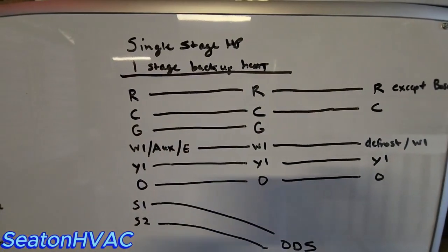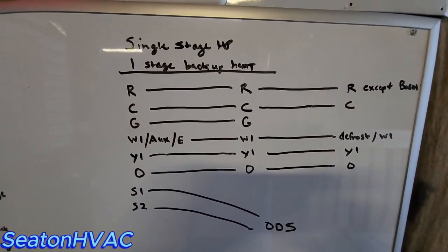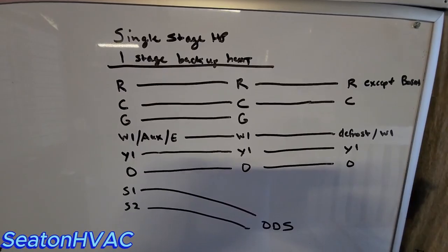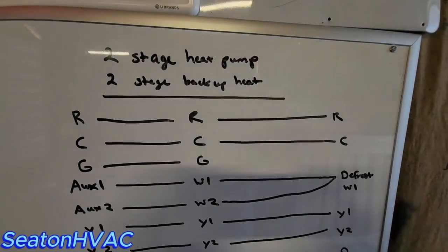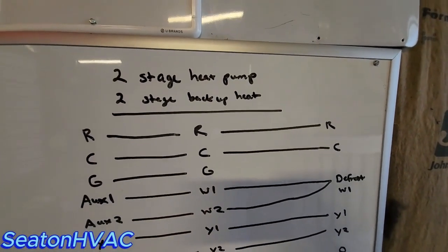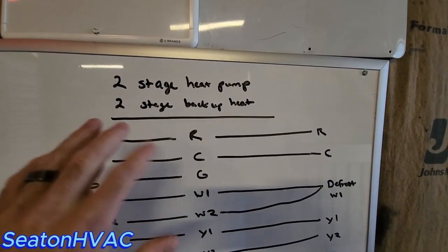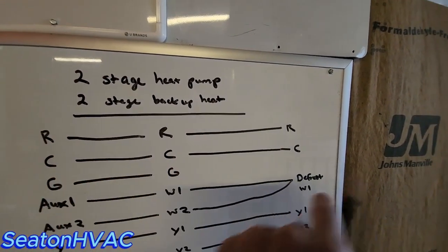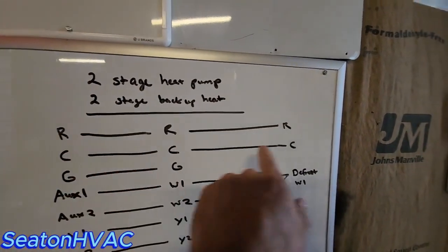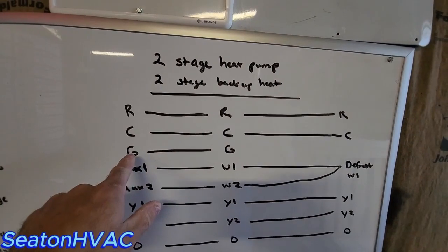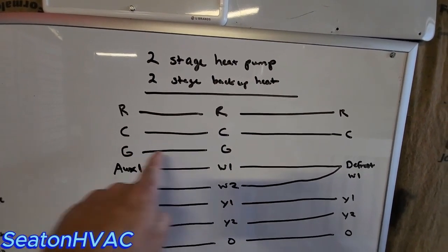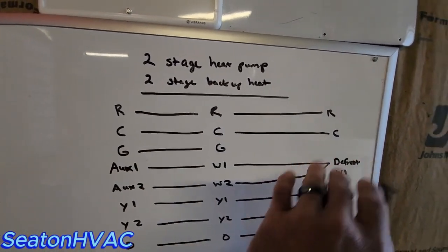Let's do a 4 heat, 2 cool scenario on this, so I can show you the most crazy setups that you'll see. Okay, guys, 2-stage heat pump with 2 stages of backup heat. So I'm not going to go over all this, and it's all the same. R all the way outside. Common all the way to outside. Fan from your thermostat to your air handler, doesn't go outside.